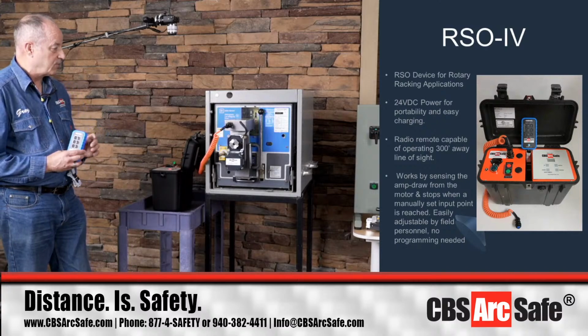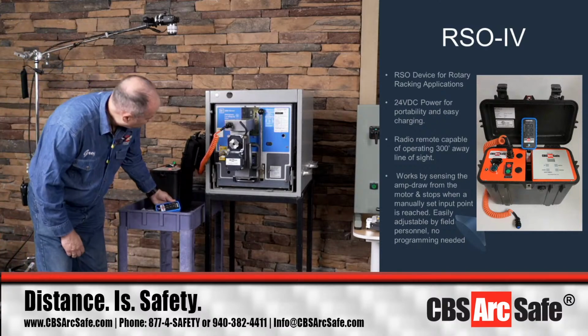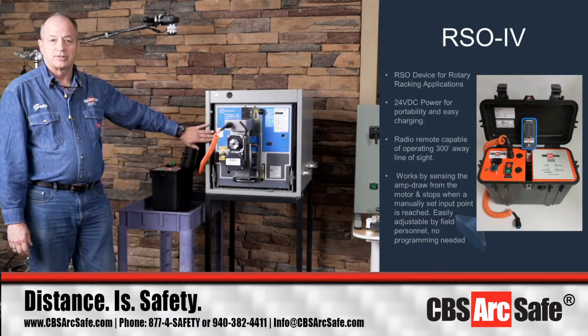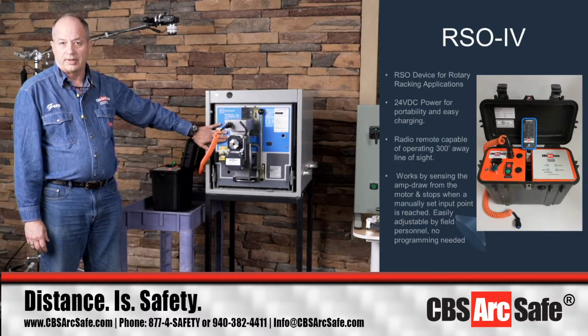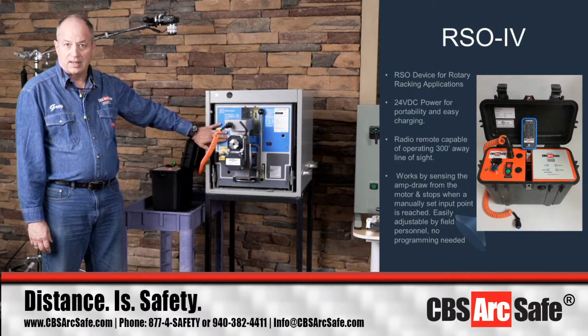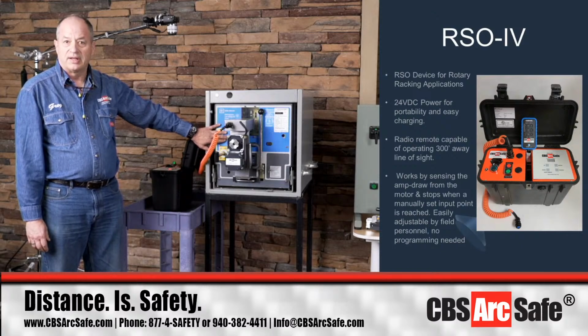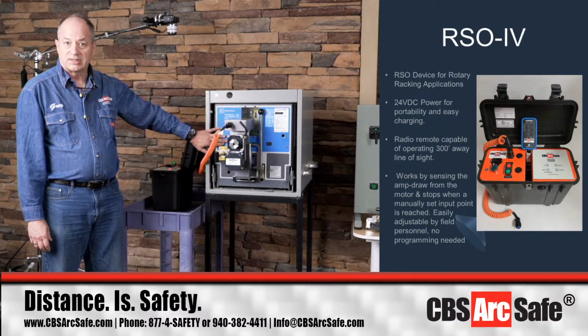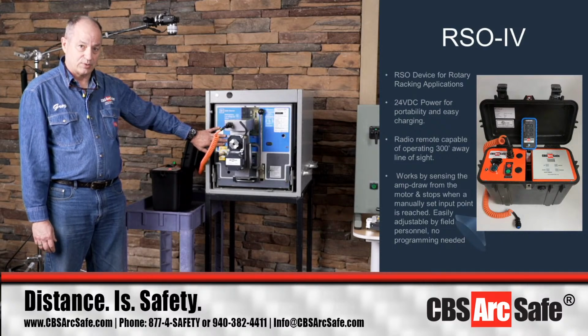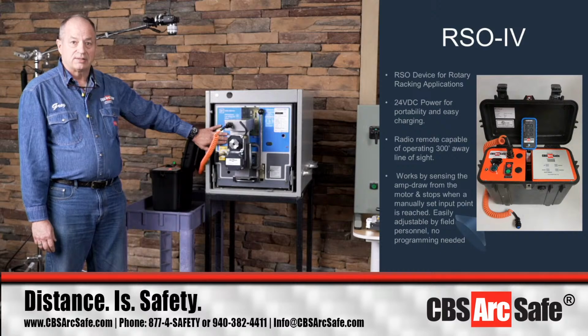Now, some of the things that I will just give you a note real quick. When you're dealing with these DS breakers, the indicator on here is a metal tab. And it's how it was installed that indicates the connect, test, and disconnect position. And to be honest, sometimes that may be off just based upon how that thing was bent. I've seen it domestically and internationally where I've looked at a breaker and I'm like, the tab looks like it's a little bit off. And I would take a permanent marker and just mark where it was showing disconnect and then where it was showing connect.